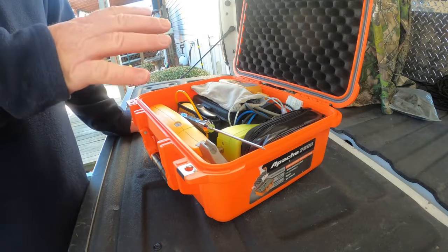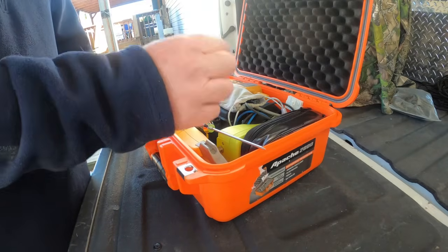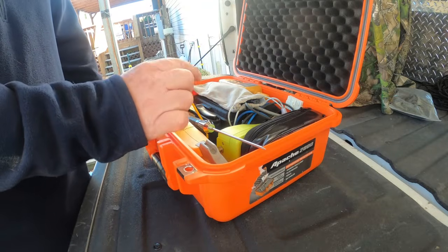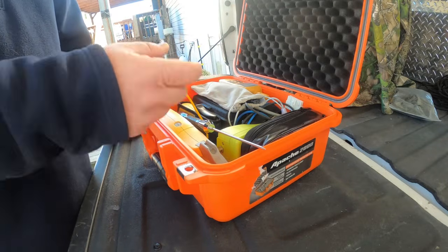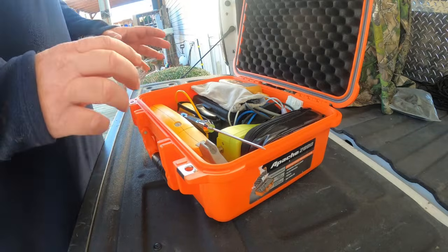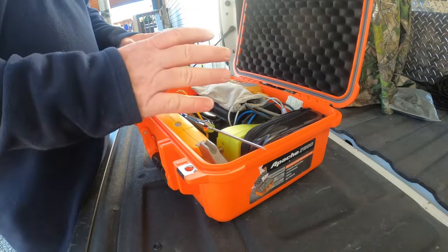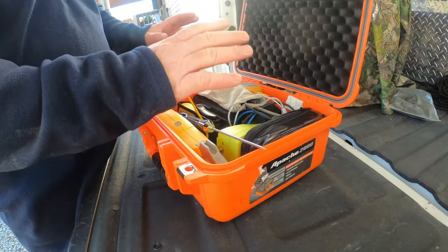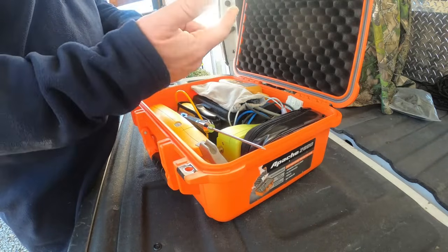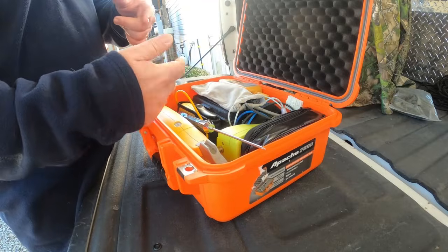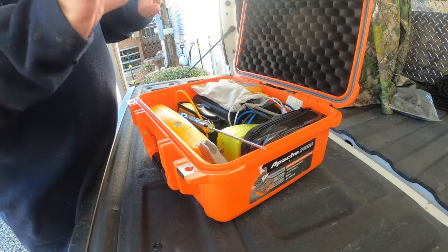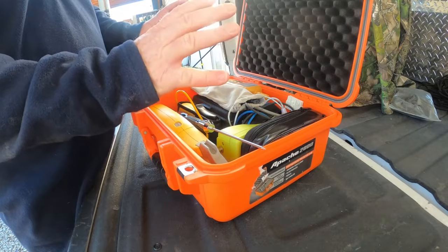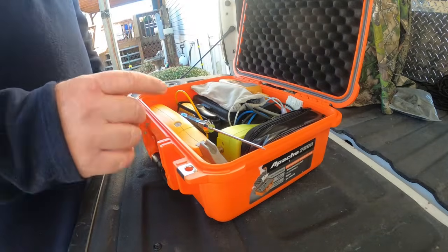When you put that motor in, you plug everything in, make sure you've got the plug set for whether you've got an air handler package unit, that's going to be 230 volts, or you have a furnace, 115 volts. And you're going to put that motor in. When you power it up, it's going to do a test run. It's going to self-determine which rotation, clockwise or counterclockwise. So when you put it in, put the door on, because it needs the proper static to set itself up. Put the door on, power it up. It's going to come on.